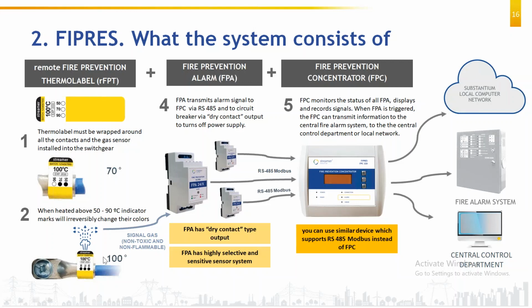The answer to the first question: the thermo label needs to be installed on all points which need overheat monitoring. So we will install on R, Y, B. If we have 3 joints on R, Y, B, we will install 9. For example, a cable comes inside the panel, there is a first cable termination, and then that termination goes to the circuit breaker. So we will install RFPT at the termination and then on the circuit breaker, on R, Y, B. Every joint needs installation.